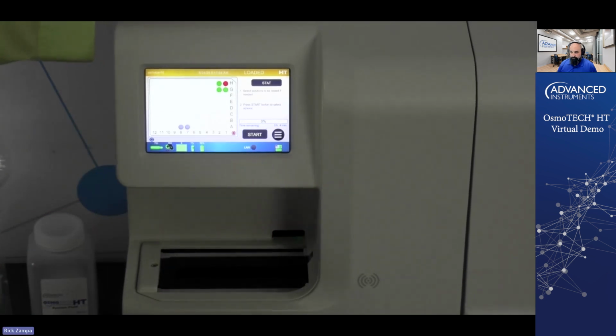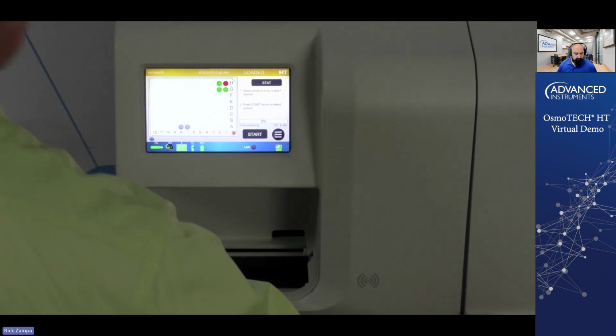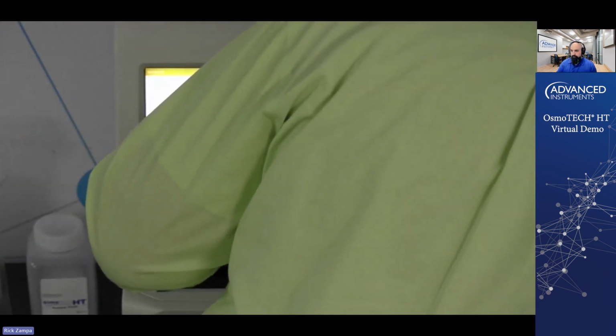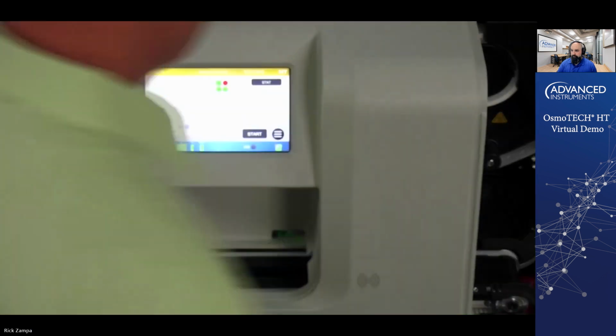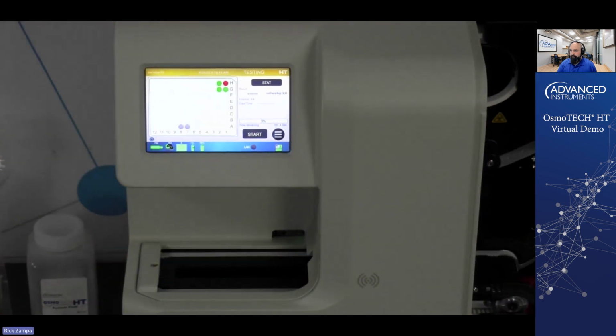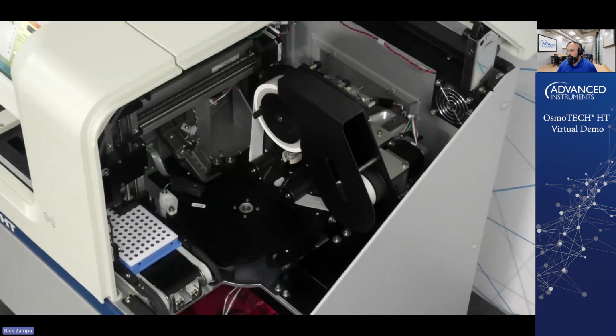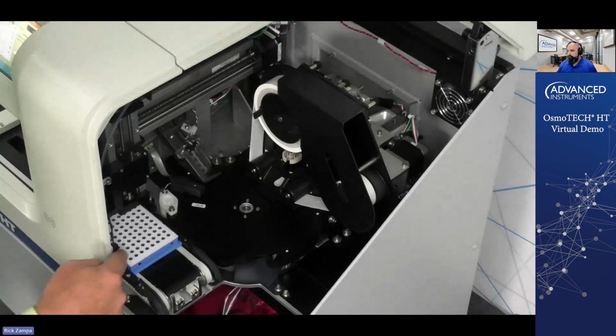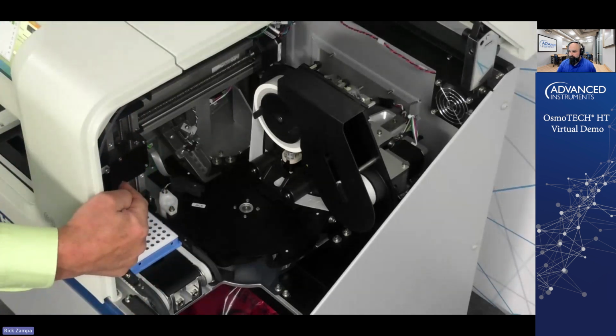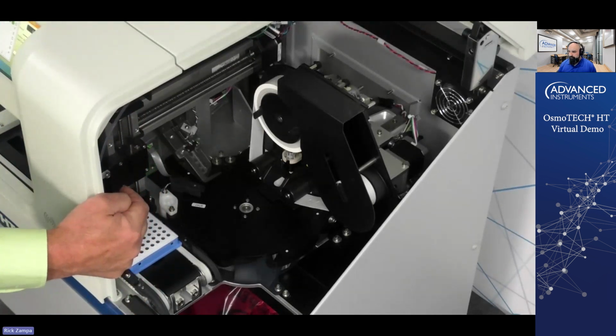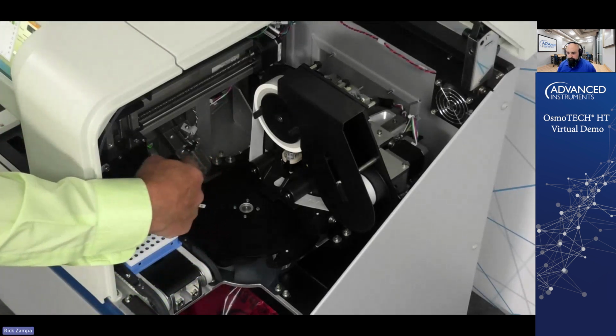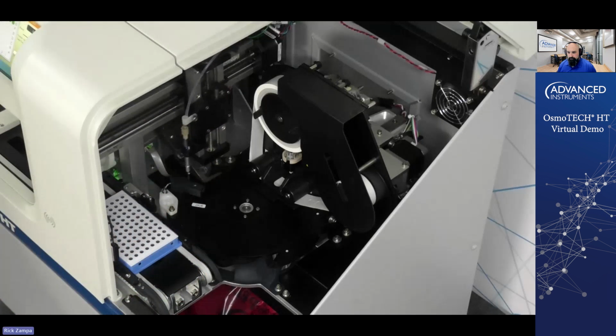So now the system will. So what I'm going to do here, excuse my reach. This is going to stop things for a second. Okay, so now what I want to do, I'm going to switch over to another camera here quickly. Hopefully, there we go. So this is the osmometer module. And what you can see is our plate here. You can see our pipette over here is pipetting the sample out of the first position well that we're looking at, which would be A7. It's then going to pipette the sample into a sample cup over here on this side. You can see the pipette moving over now.